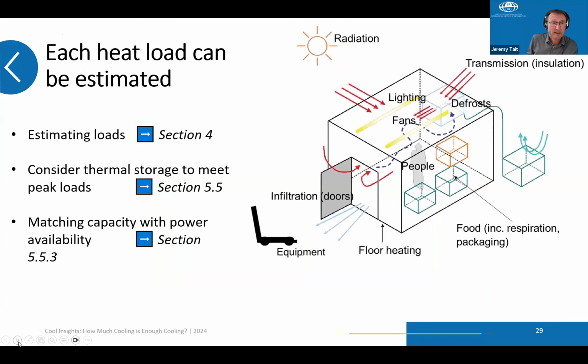In the guide, there's a substantial section that leads you through estimating what that heat load might be, describing the different heat loads that occur. They're summarized on this diagram, ranging from solar radiation on the outside of the unit, which increases heat transfer through the insulation, to heat coming in from the produce - especially if it's warm from the field. You've got energy from fans and lighting, all of which ends up as heat. You've got people going in and out, bringing heat and humidity with them. And there may be heating to make sure the door seals don't freeze. All of these things increase the heat load.